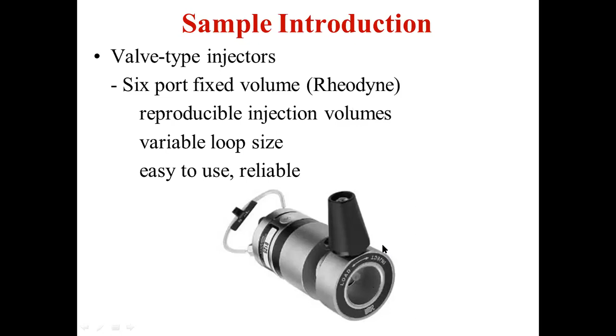Before introducing the needle into this port, you have to adjust the positioning of this knob to the load. Then you have to introduce the syringe needle. Then if you rotate this towards the injection mode, you introduce the sample to the column. It means it will open the loops for the movement of the solution towards the chromatographic column.